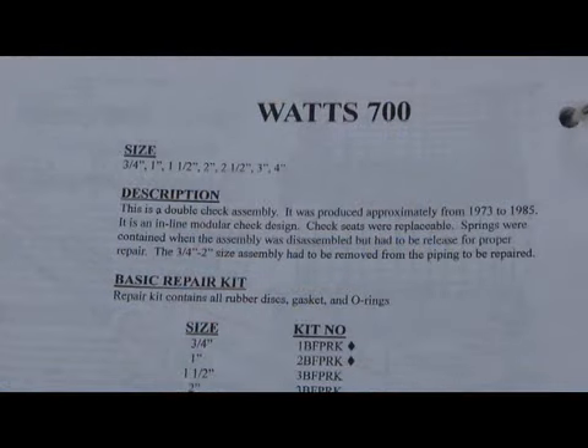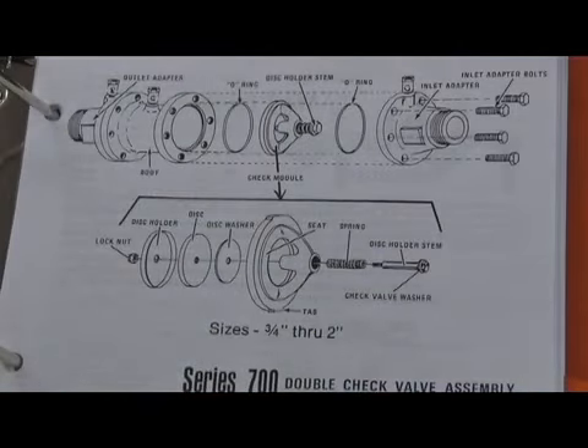The next assembly we're going to discuss is the Watts 700 double check assembly and the 900 reduced pressure principle assembly. This was produced in sizes three-quarter through four inch. The 700 double check was produced from about 1973 to 1985. The 900 RP series from about 1970 to around 1988. Both the 700 and 900 series had to be removed from the body for repair.